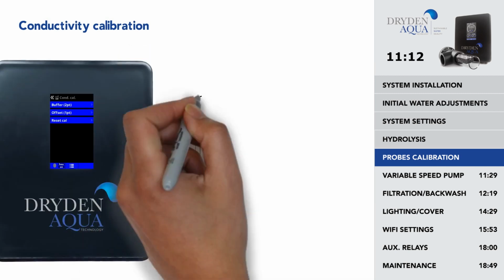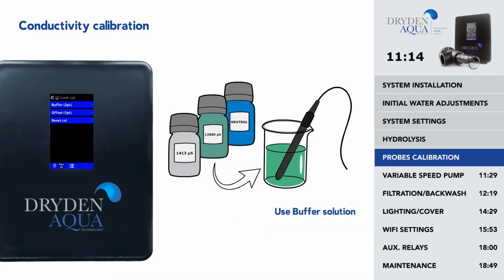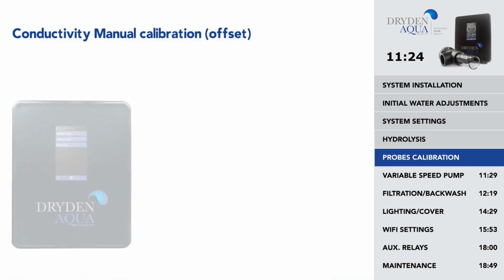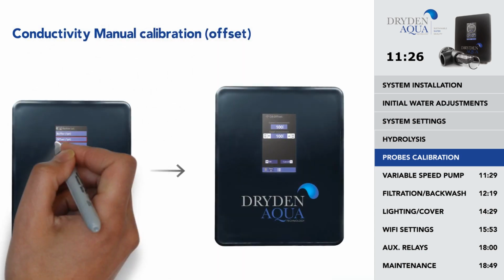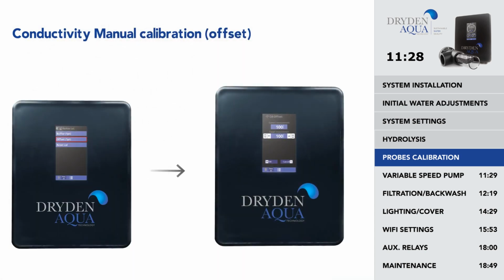Always do the first calibration with buffer using the adapted buffer solutions. Press on buffer and follow the instructions in 7 steps that appear on the display. Manual calibration of the conductivity probe is also possible, but is not recommended.